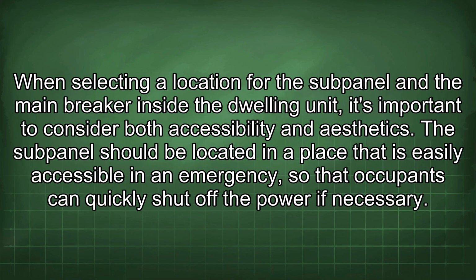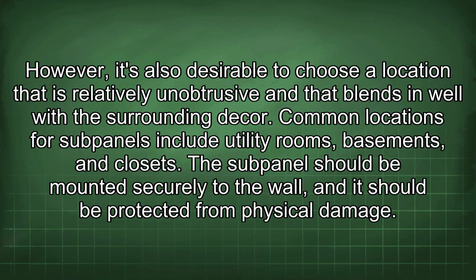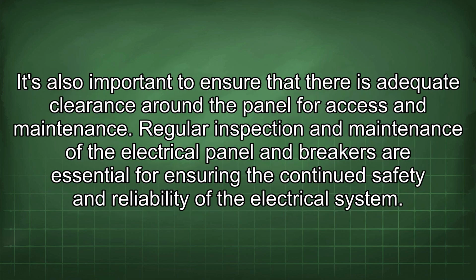hazards. When selecting a location for the subpanel and the main breaker inside the dwelling unit, it's important to consider both accessibility and aesthetics. The subpanel should be located in a place that is easily accessible in an emergency, so that occupants can quickly shut off the power if necessary. However, it's also desirable to choose a location that is relatively unobtrusive and that blends in well with the surrounding decor. Common locations for subpanels include utility rooms, basements, and closets. The subpanel should be mounted securely to the wall, and it should be protected from physical damage. It's also important to ensure that there is adequate clearance around the panel for access and maintenance.